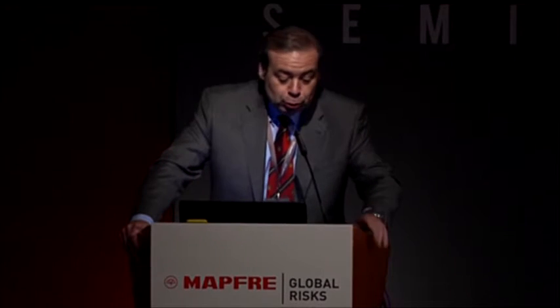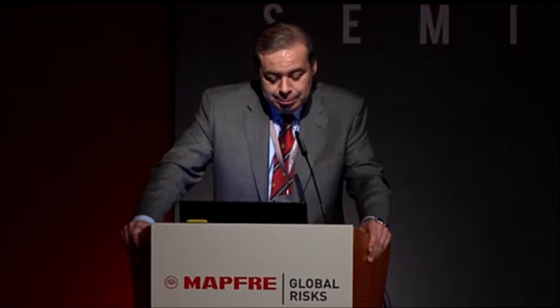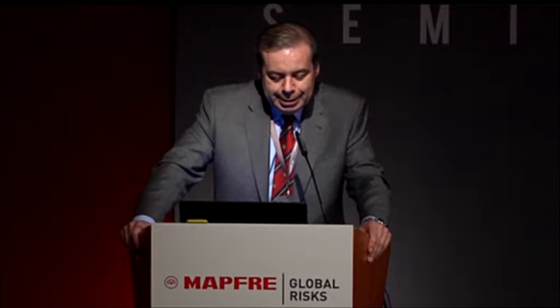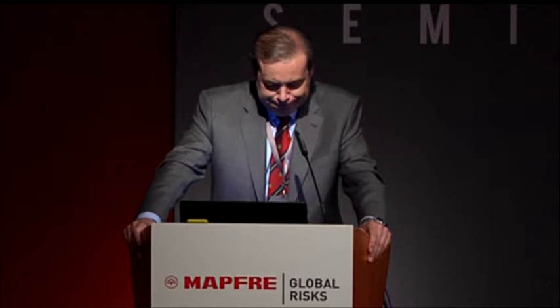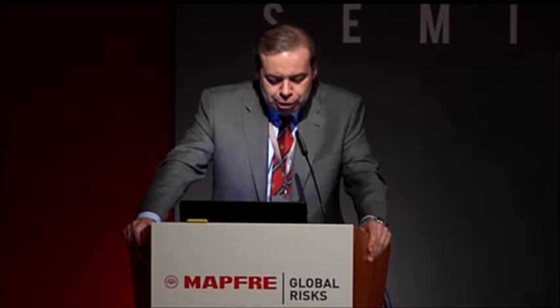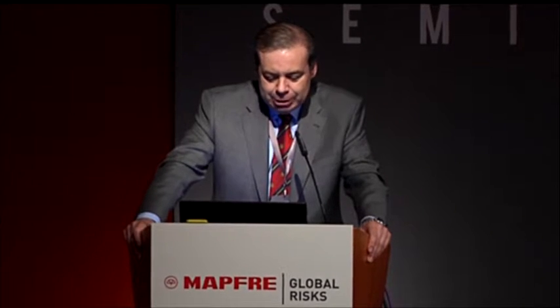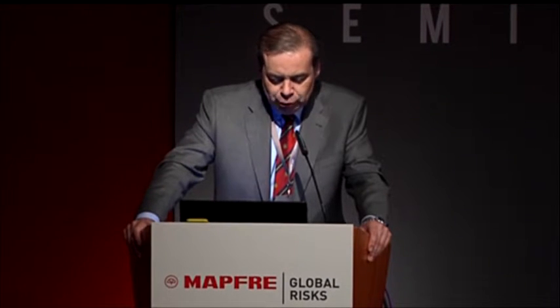And we have technology experts and vendors in the room. And if I may say, perhaps at that time, some turbines were sold and commercialized with insufficient operation hours. We had the challenge of reaching 60% yield in combined cycle, and the conditions in which the turbines operated were extremely demanding. The elements that have suffered most and that have caused a greater number of incidents are the blades. Later on, I'll explain to you the different degradation phenomena that affect the blades in gas turbines.